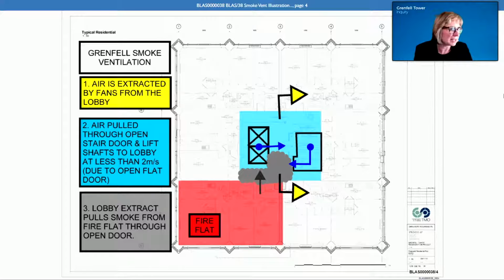I wouldn't say you're pulling it from the fire flat. The smoke coming from the fire flat will naturally have momentum along the corridor. But in this system where you've depressurized the lobby by extracting air from it, when you open the fire flat door, do you accept that the low air pressure in the lobby would mean smoke was drawn out into the lobby? Not for the reasons you say.